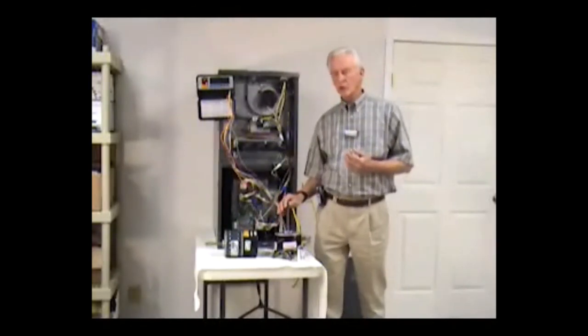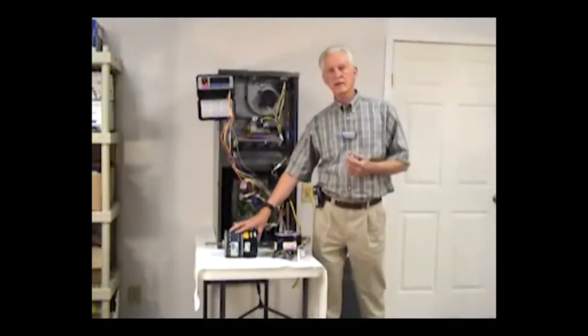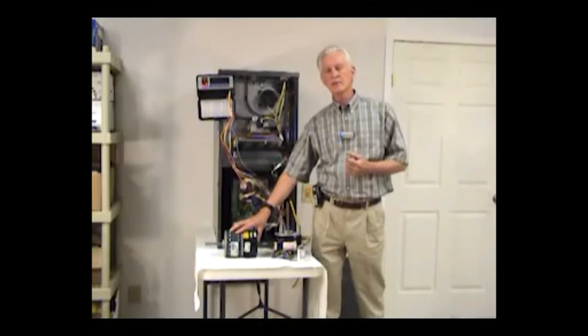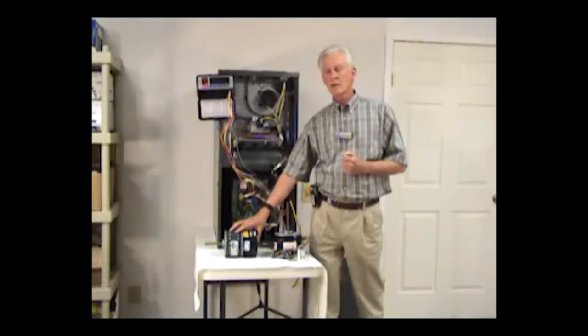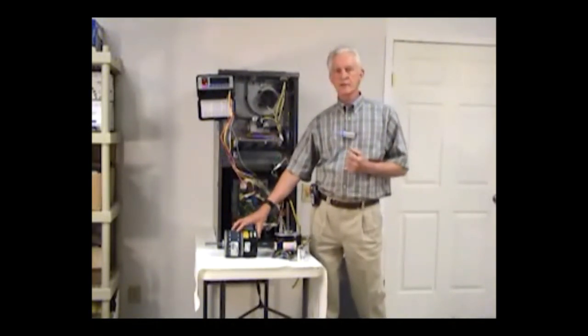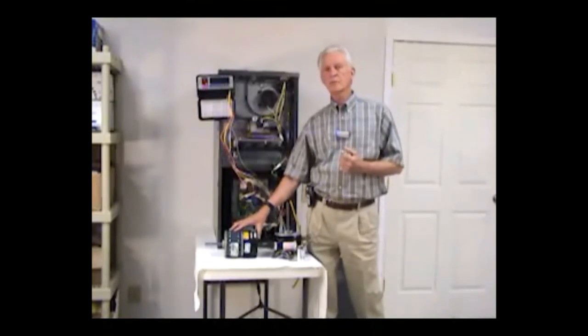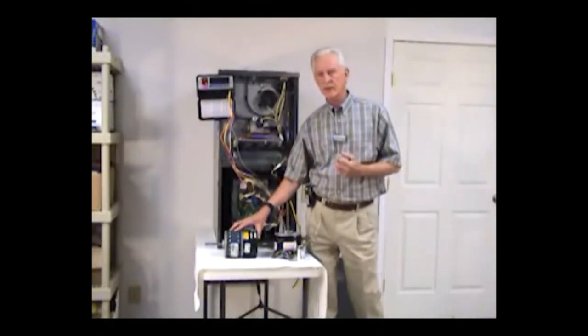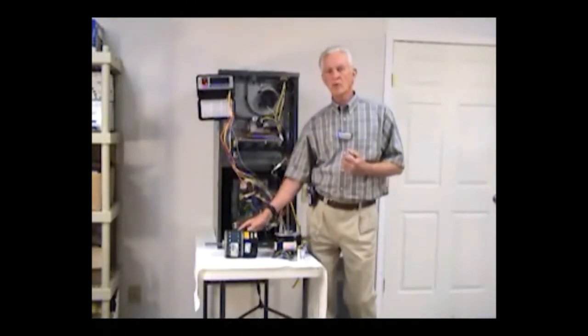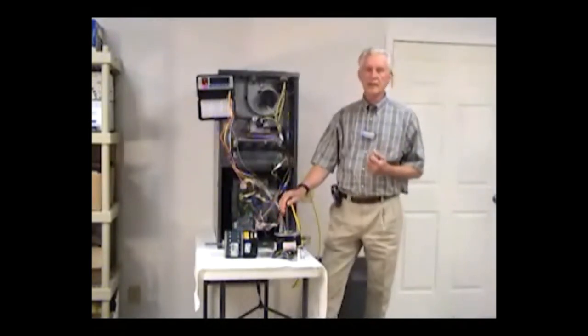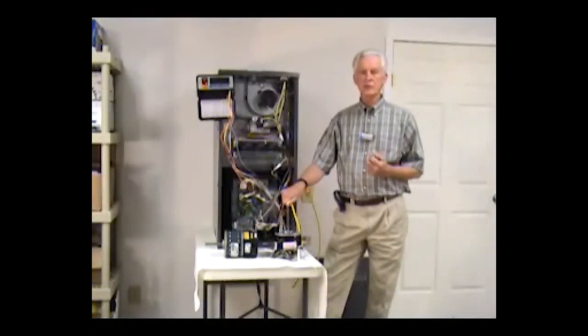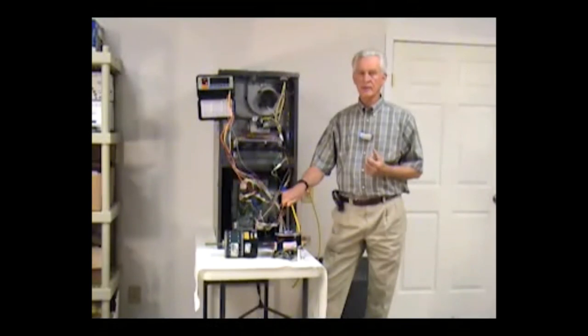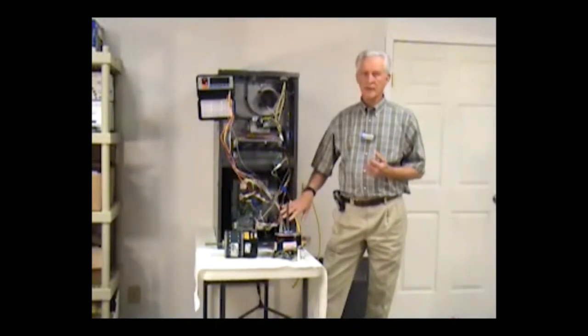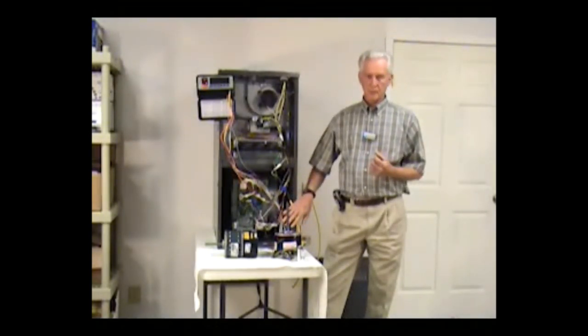Once we pass 0.5, we're still at a point at which we can deliver the required amount of CFM, and we'll go back to the 1200 CFM of air, and we'll say this motor is delivering 1200 CFM of air. If we are at 0.5, it's delivering 1200 CFM. If we are at 0.7, it's delivering 1200 CFM of air. All the way up to a full inch of static, it could still continue to deliver 1200 CFM of air, if we are having filter load up with dirt.